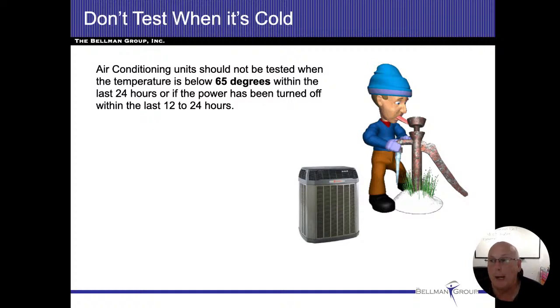Now, the reasoning why we don't want to test air conditioners at a lower temperature, I need you to go back to your memories a little bit to when I showed that compressor out there earlier. An air compressor can only compress air, all right? If I try to push liquid through that compressor, all I'm going to do is damage it, plain and simple. So you might go to a house, you're inspecting the home, and the air conditioner might be just fine. But you turn it on and the refrigerant around that compressor is a liquid. Now you're pushing that liquid through the compressor, and that's going to damage the scroll coils and everything else. So we don't want to take that chance. We don't want to damage the compressor whatsoever.